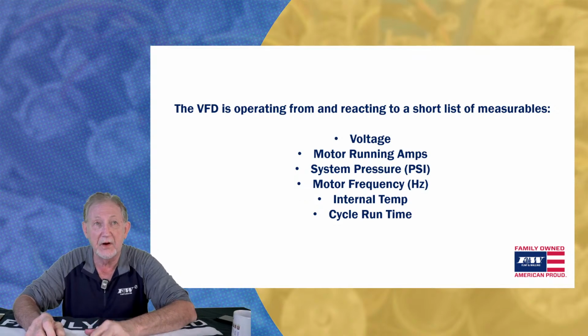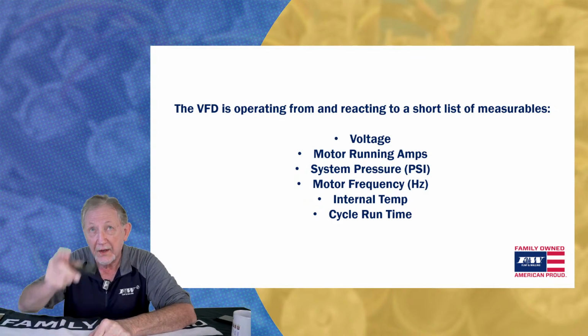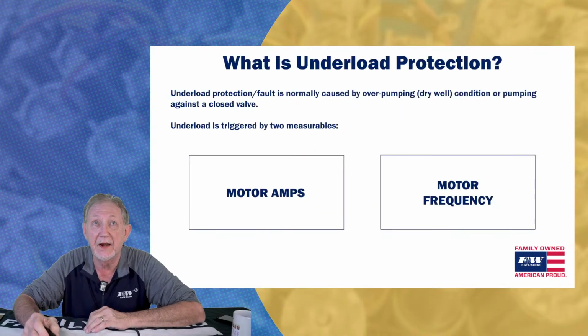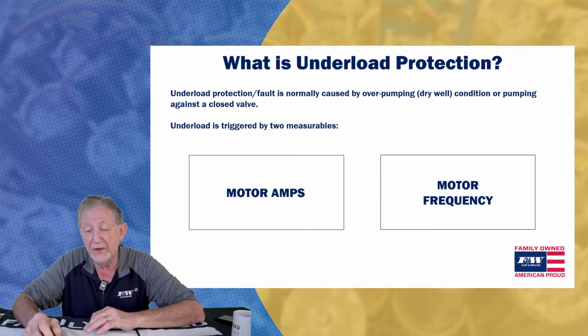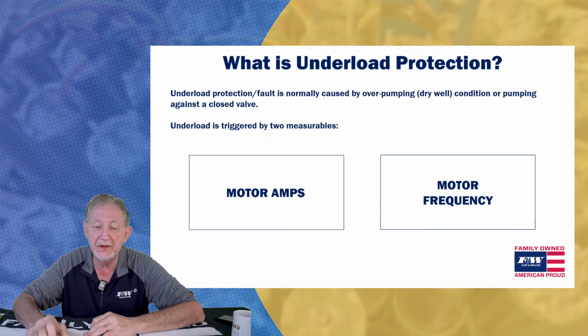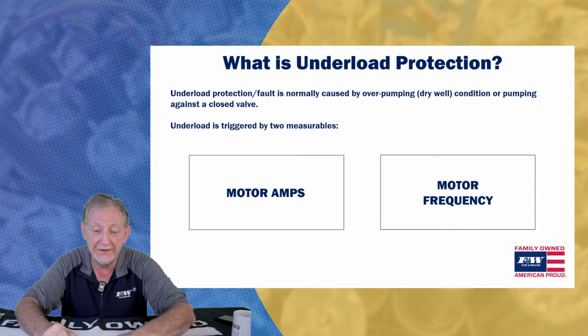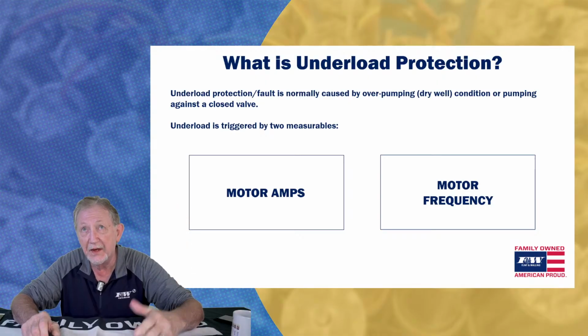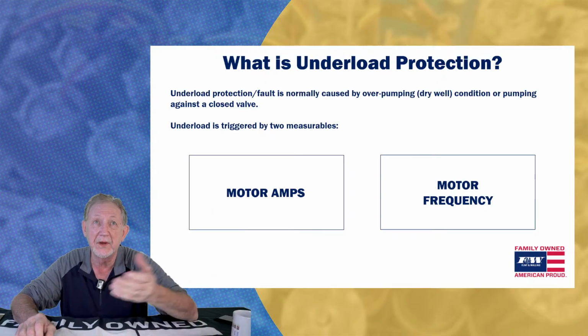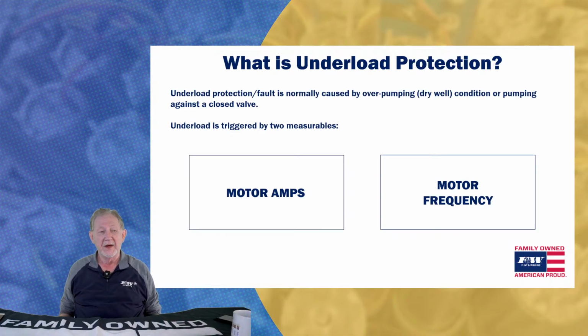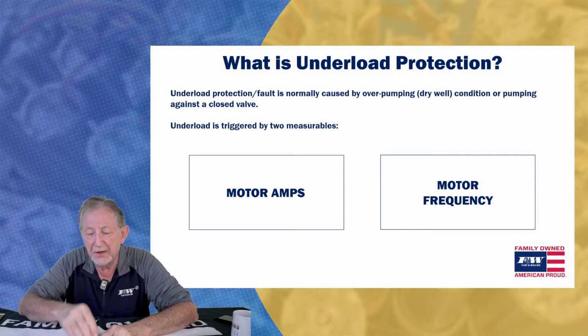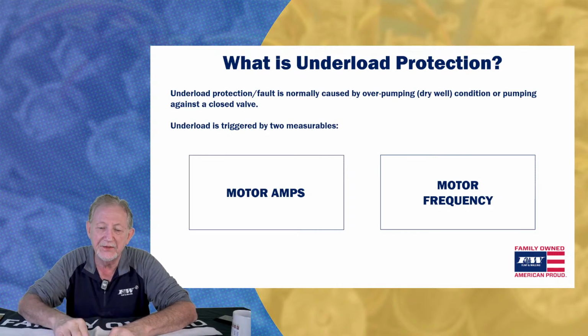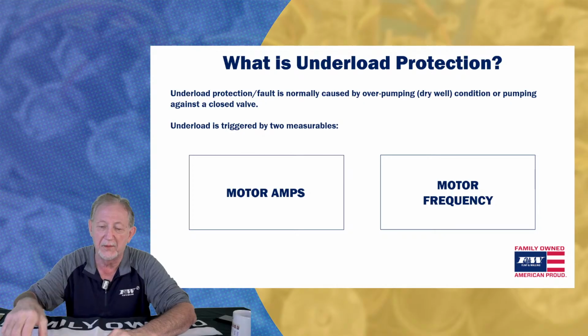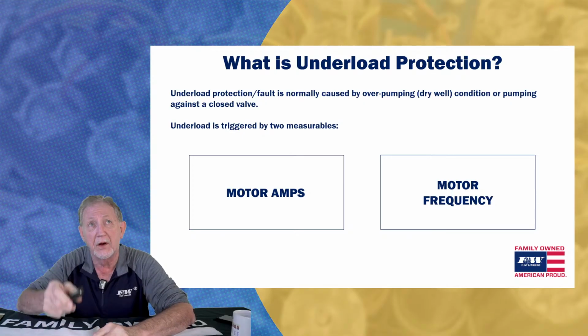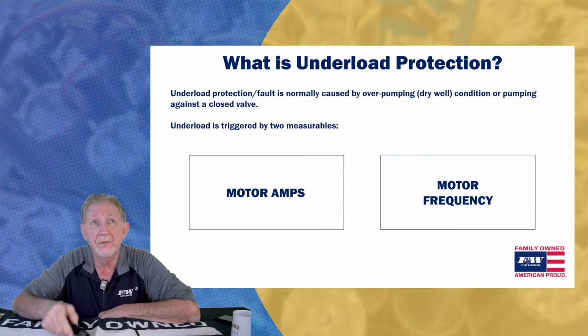So keep that in mind. A lot of people think that drive ought to know whether water is being used or not. Oh no, it knows what's up there on that screen. So what is underload? What do we talk about when we have underload protection, right? Well, underload's typically going to occur if you have a pump that's running dry, all right? Not something that we like to see happen, but if a water table has dropped down and you've got a pump that's running dry, you're going to be in an underload condition. Same thing would happen if you have a pump that's pumping against a closed valve. That condition is called deadheading. Very, very destructive for a pump to be in that kind of condition. But either one of those is going to trigger an underload by these two measurables.